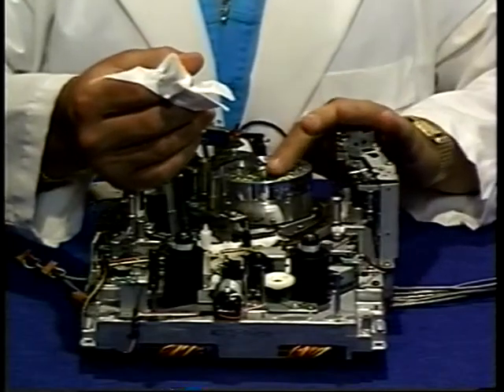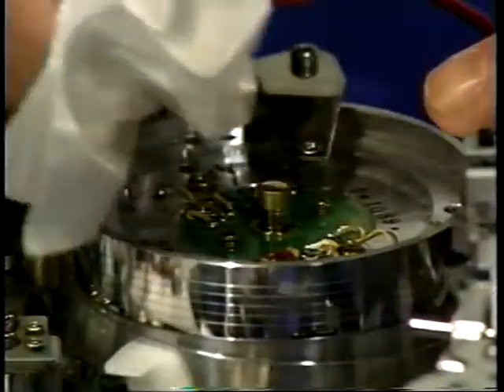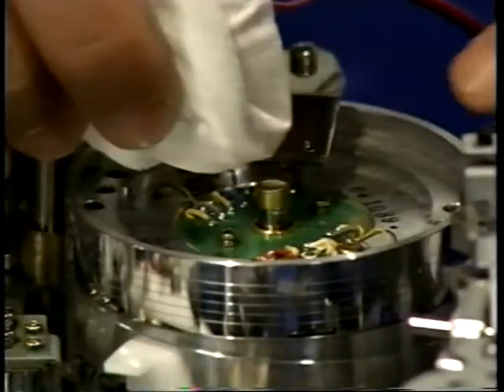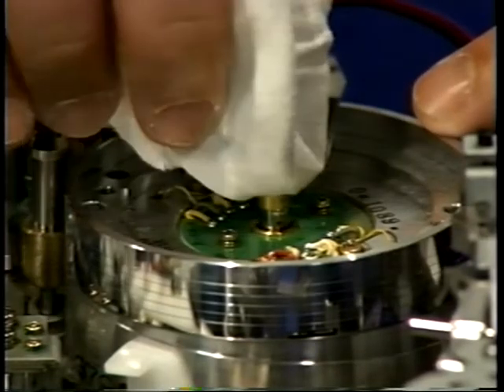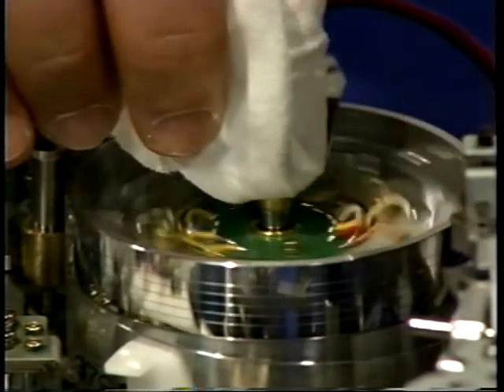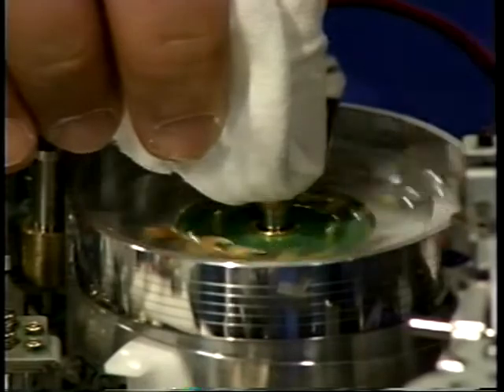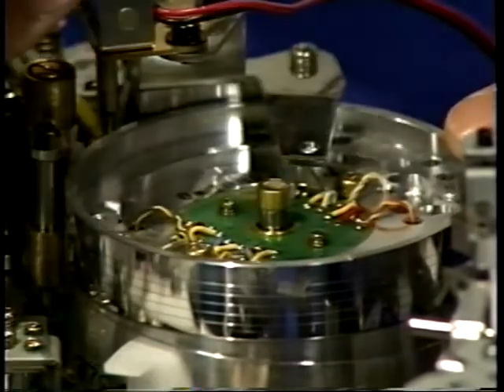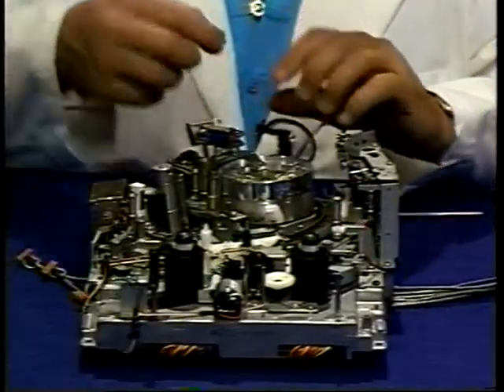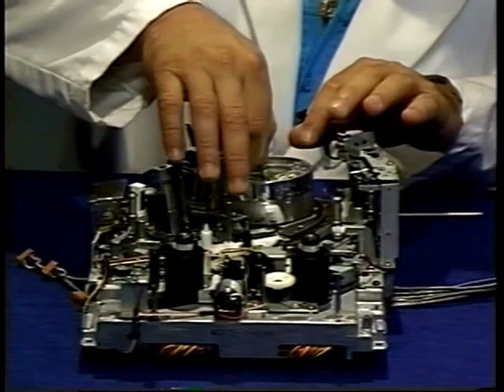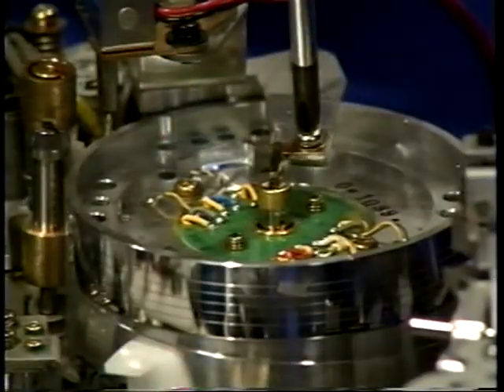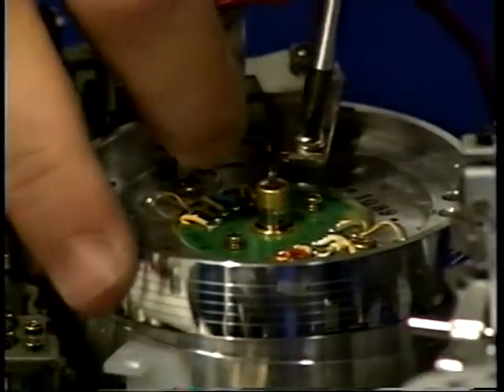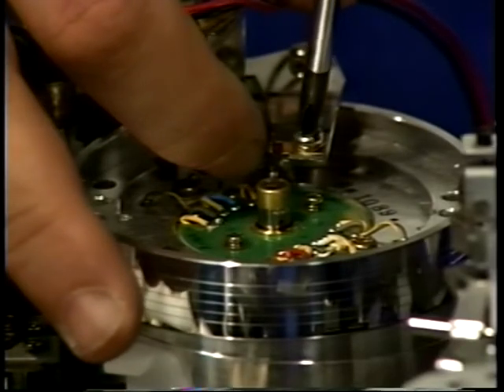Next, clean the slip assembly located here. Using an alcohol-moistened Tex wipe on your finger, clean the top of the assembly while rotating the upper drum to remove any deposits, making sure it is clean and shiny. Now replace the slip assembly and earthing brush. While tightening the screw, hold the brush with your finger to make sure it is centered on the slip assembly.